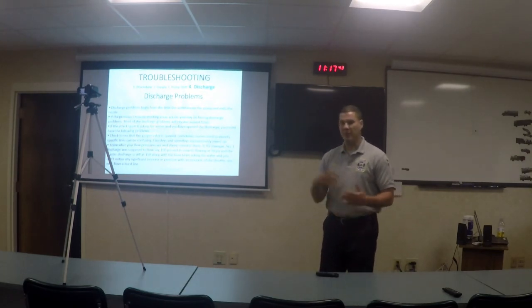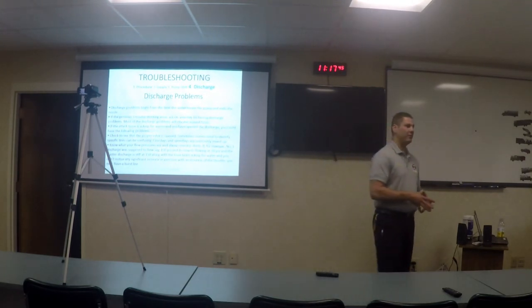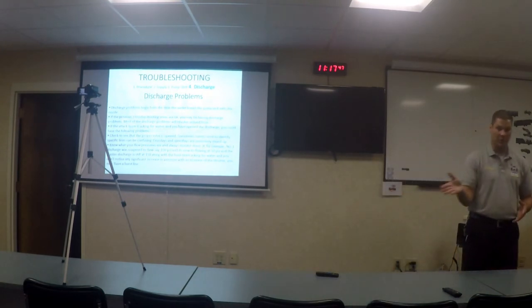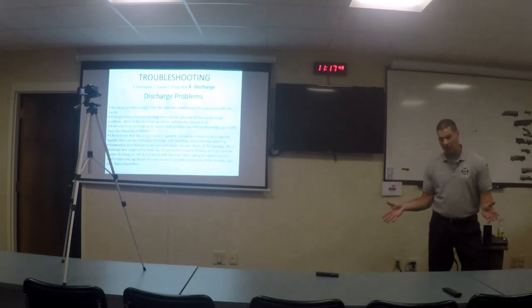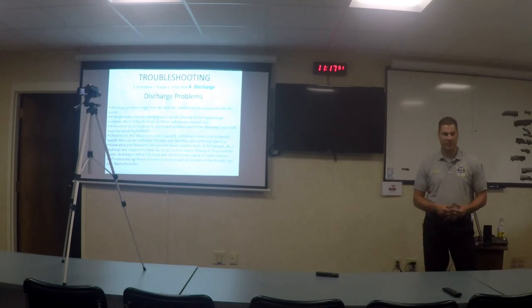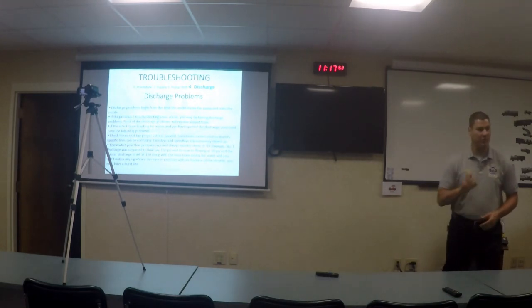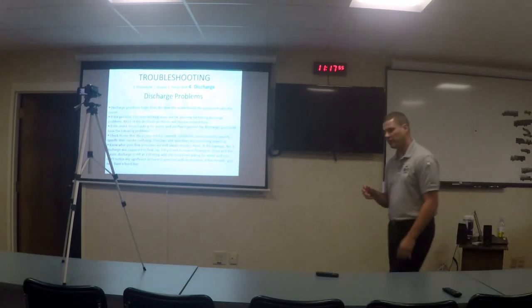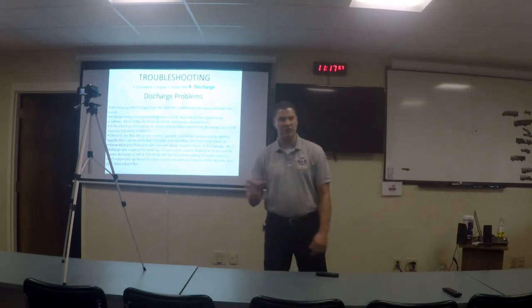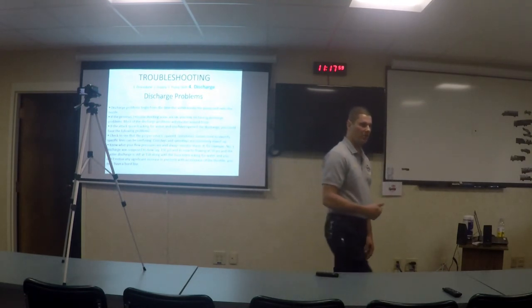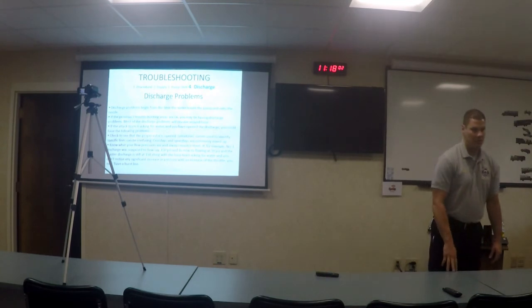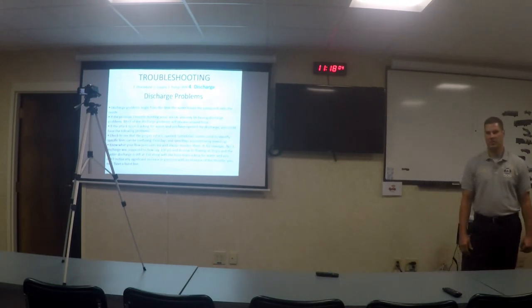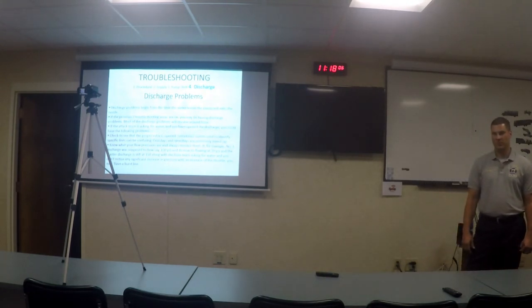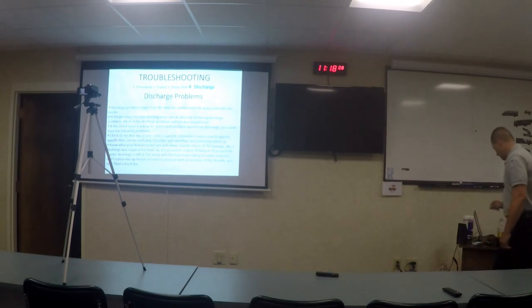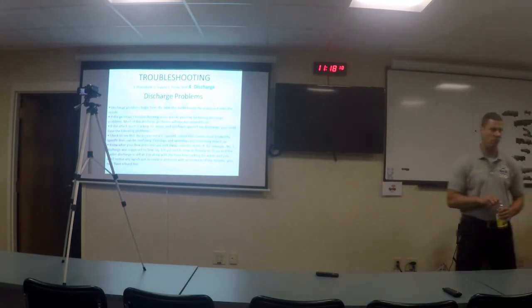If the line was set at 150 and now it's at 50, or lower than what it was set at, what do you think the issue is? You probably have a burst line. What if you're throttling up because they ask for more pressure, and the pressure stays about the same, but they're still asking for water? Pressure staying the same, or right around the same - could be a kink, no?